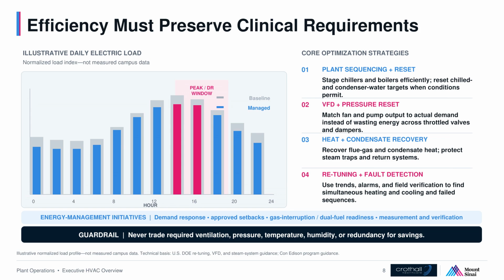The first energy rule is a guardrail. Never trade required ventilation, pressure, temperature, humidity, filtration, or redundancy for savings. Within that boundary, the biggest opportunities are operational. Sequence chillers and boilers so the efficient combination runs. Reset chilled water, condenser water, and pressure targets when outdoor conditions, space requirements, and system design permit. Use variable frequency drives to match fan and pump output to demand instead of wasting energy across throttled dampers and valves. Recover flue gas and condensate heat, and keep steam traps and return systems healthy.